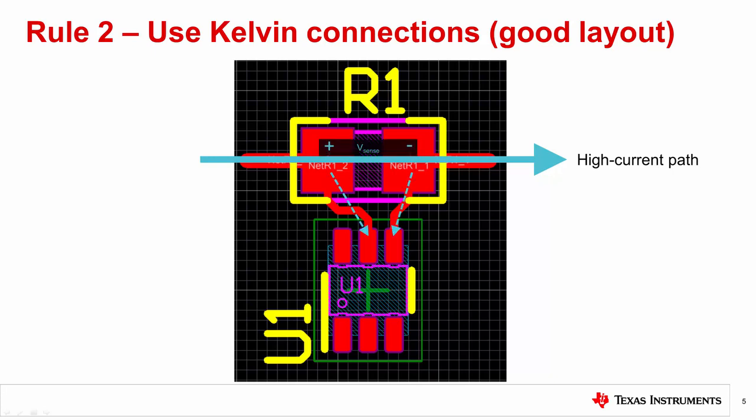There are Kelvin connections from the resistor pads to the amplifier which provide the differential voltage to be measured. Trace lengths are very short. The current flowing through these traces is minimal, usually around tens of microamps, so the voltage loss on the path from the resistor to the monitor is very low.